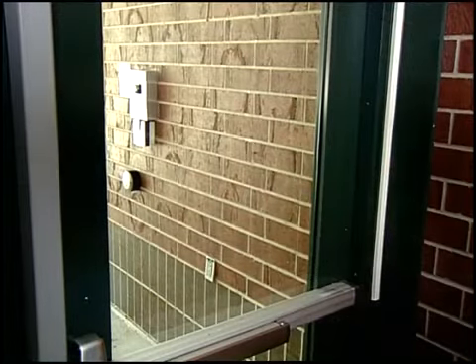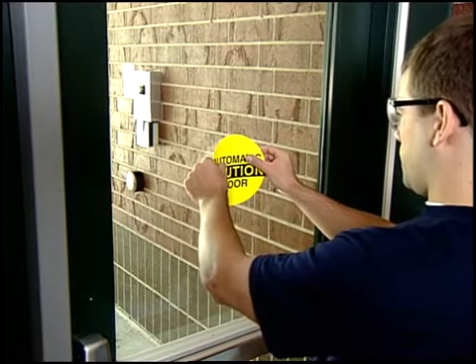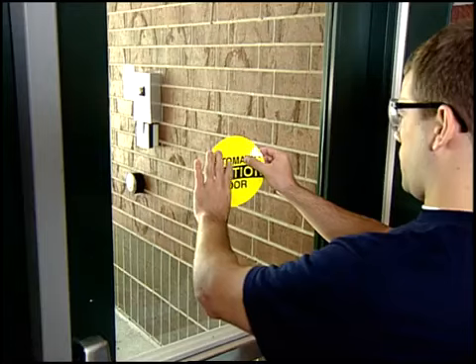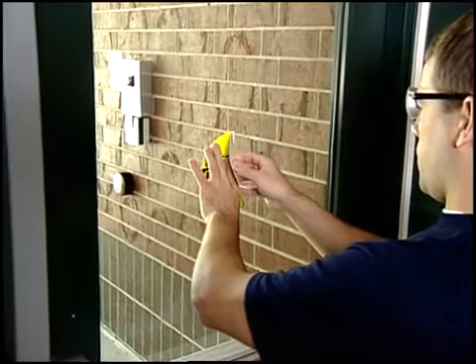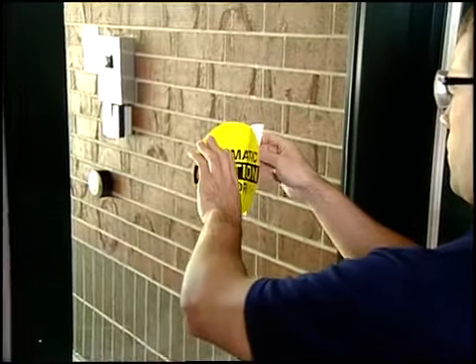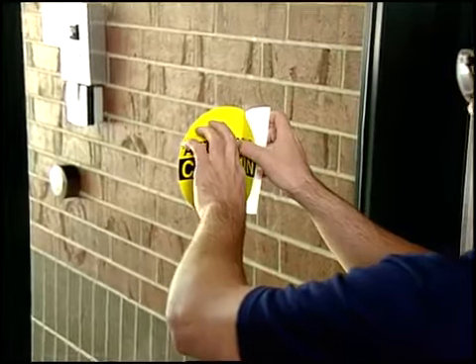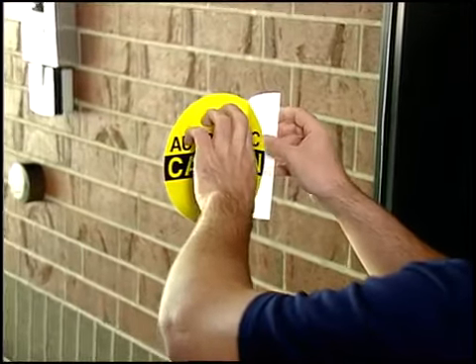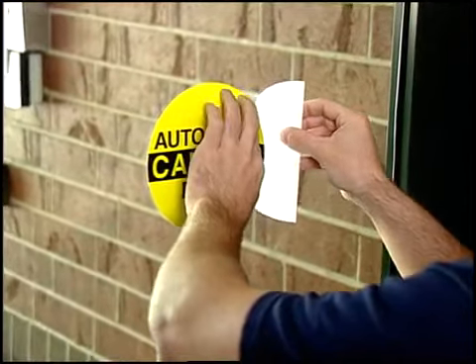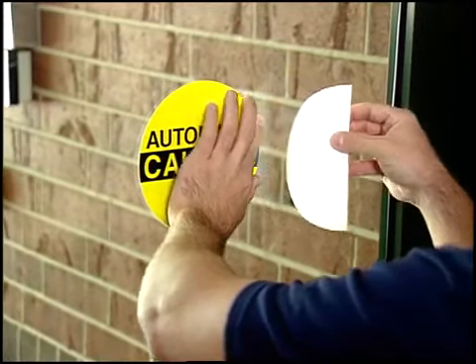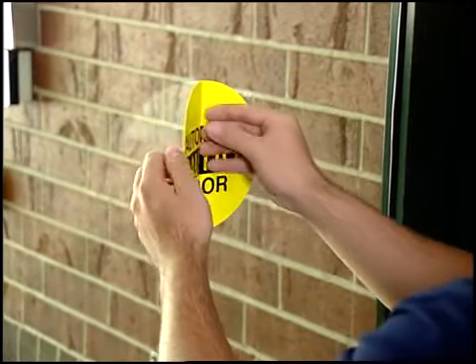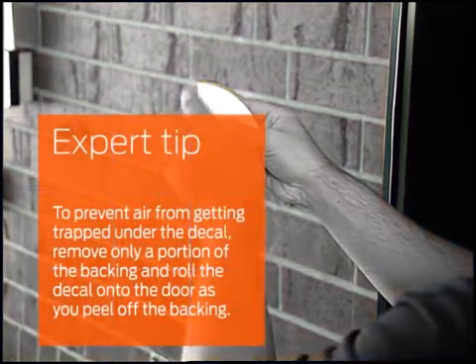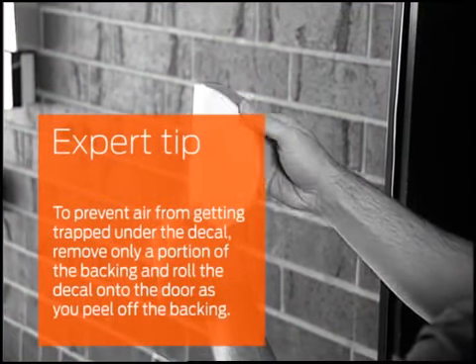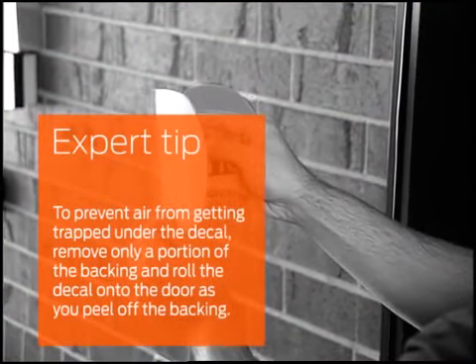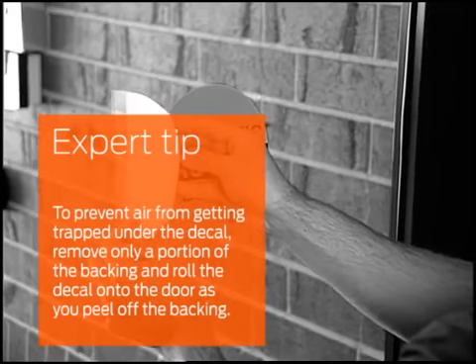Finally, locate the 2 caution automatic door decals in the kit. Place 1 or 2 decals on the door near the latch area. By code requirements, the decal must be located at 58 inches, plus or minus 5 inches, from the floor to the center line of the sign, and must be visible from both sides of the door without interference. To prevent air bubbles from getting trapped under the decal, remove only a portion of the backing and roll the decal onto the door as you peel off the backing.